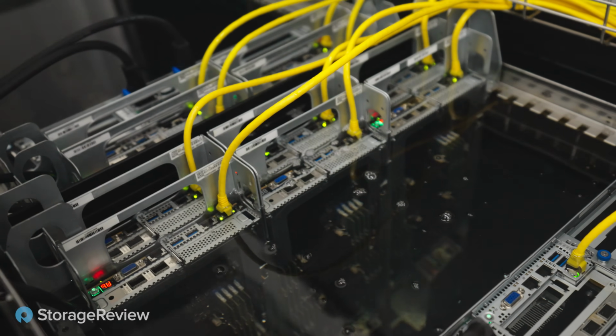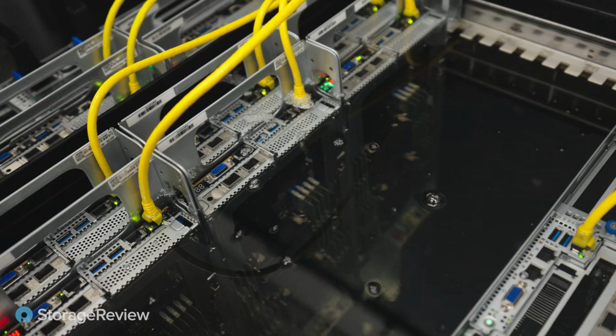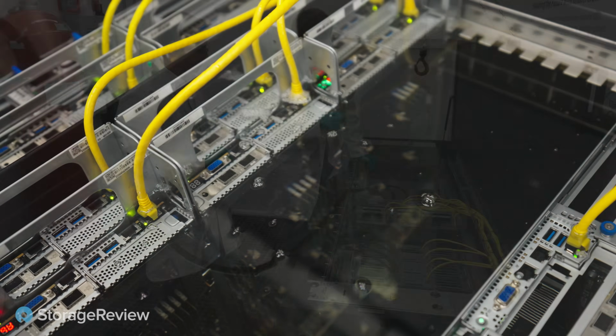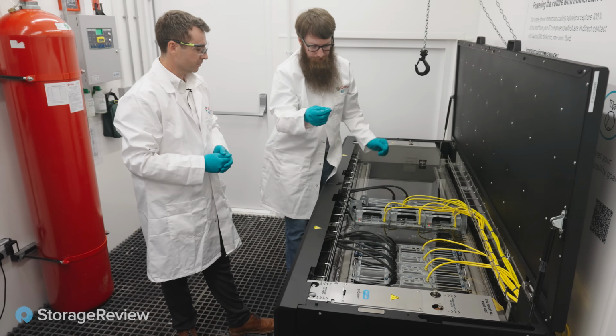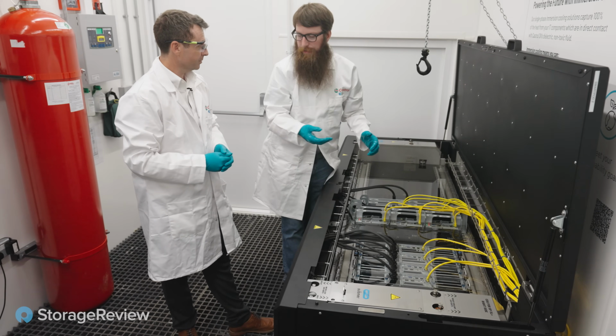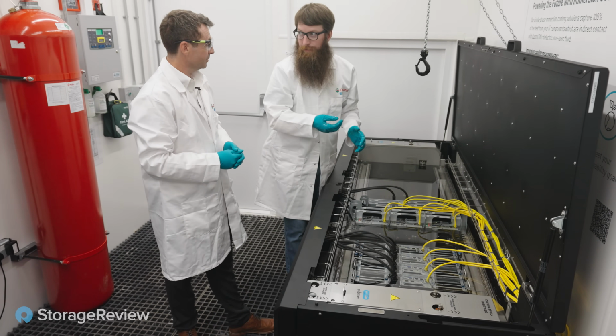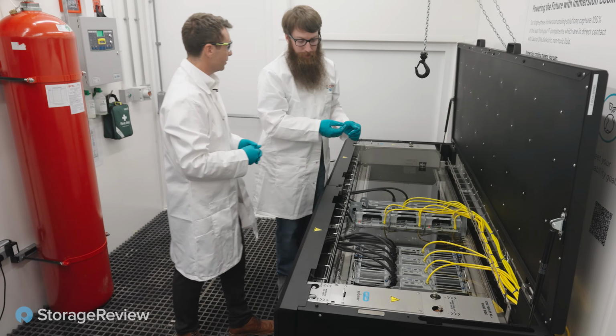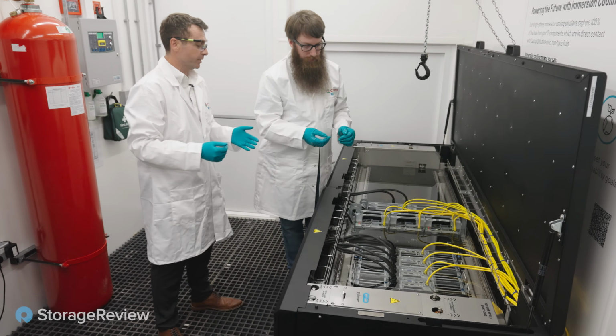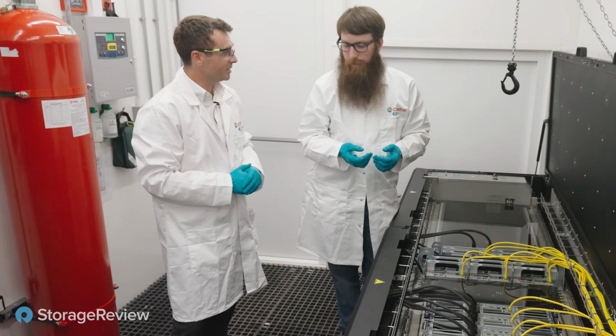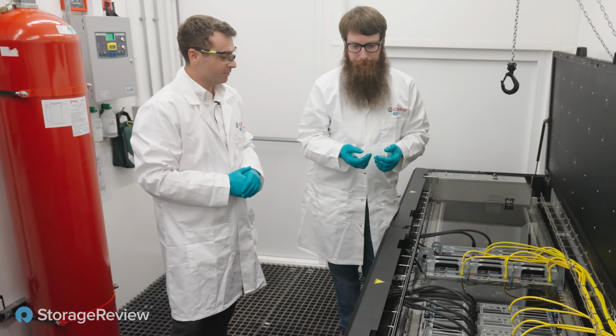Is there any consideration for the connected interface between the DRAM? We just put that DRAM back in without cleaning off the slot. Will it still make good connection? Yeah, exactly, because it's made to work with the fluid. So it's just a small mindset change of having liquids in your data center, but immersion cooling really is that simple.